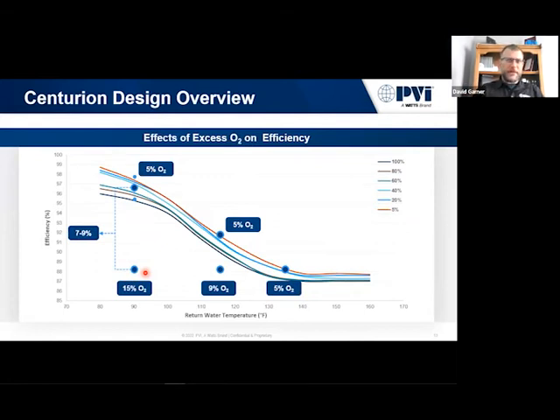This is one of the reasons a lot of manufacturers stress to make sure you go through and do the yearly maintenance and tuning of the equipment, because if your combustion gets completely out of whack, you can run into issues where the unit might not light, your efficiency nose drops, and it's just going to really impact how that system works.